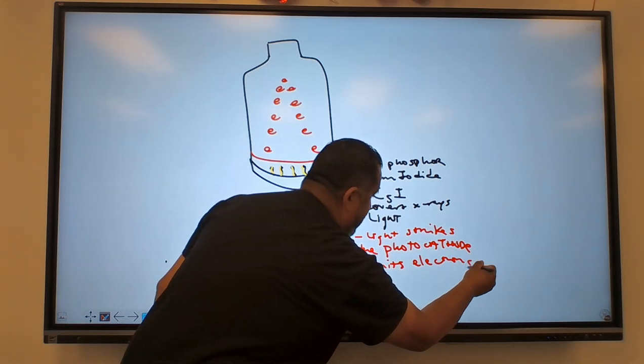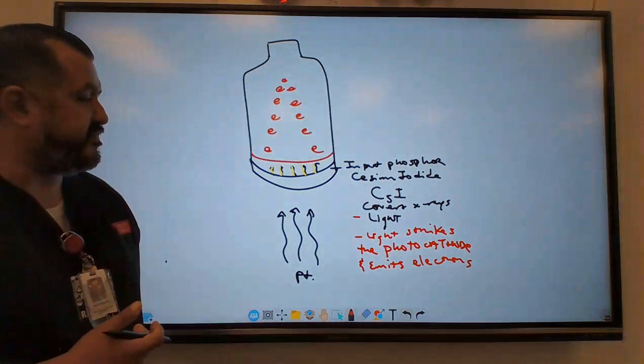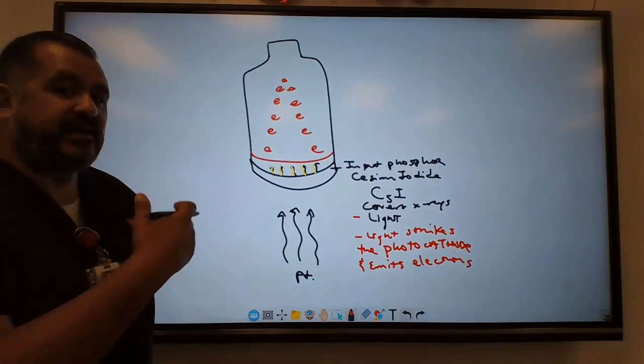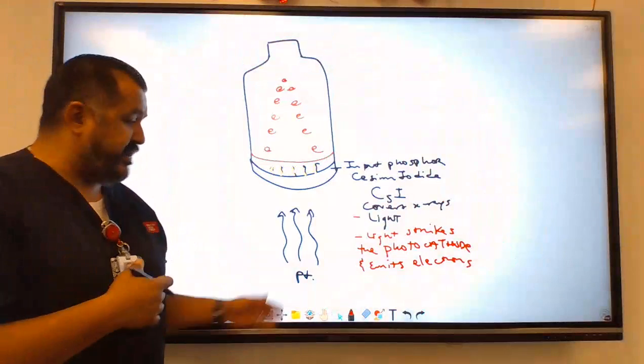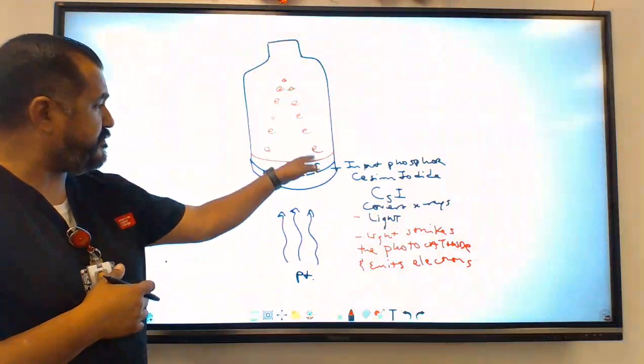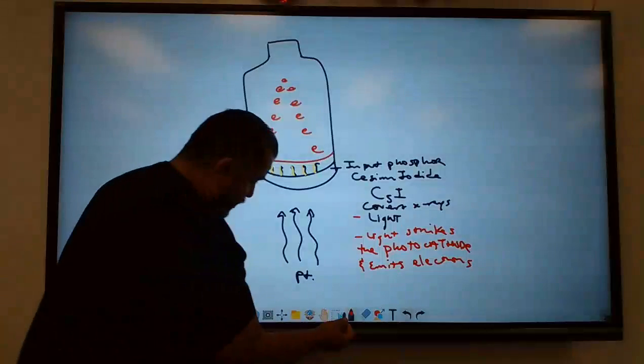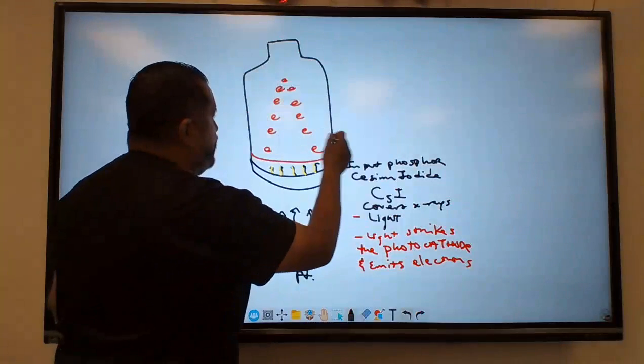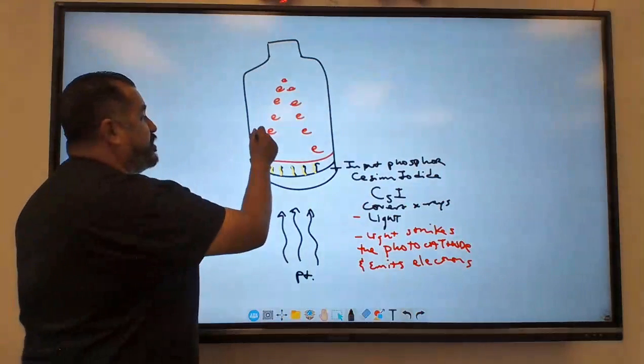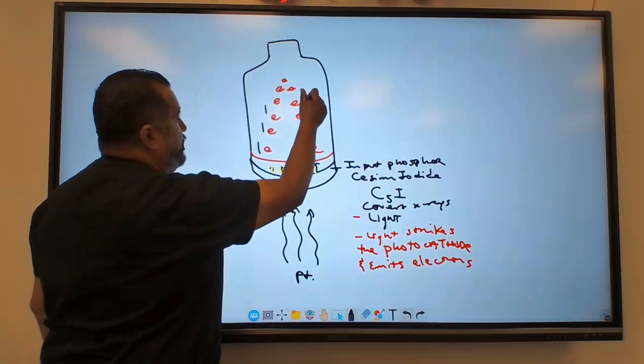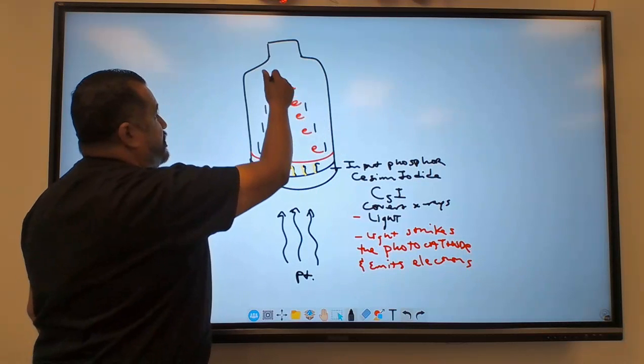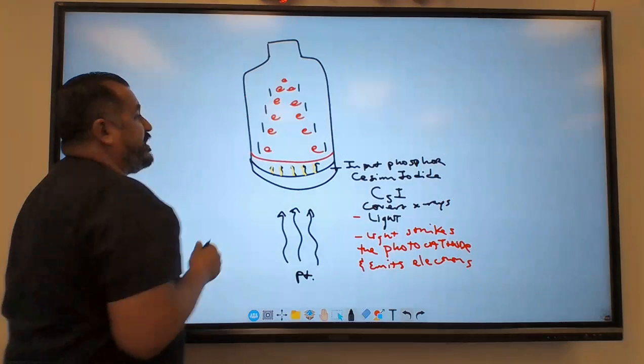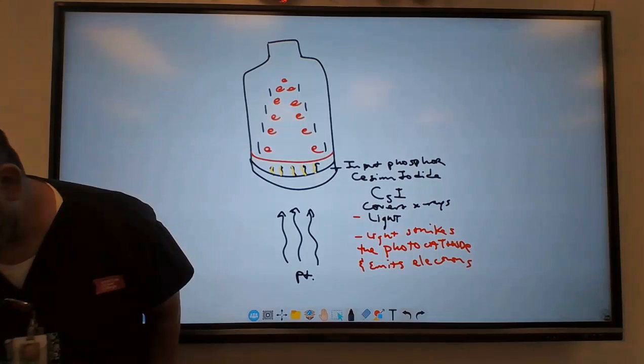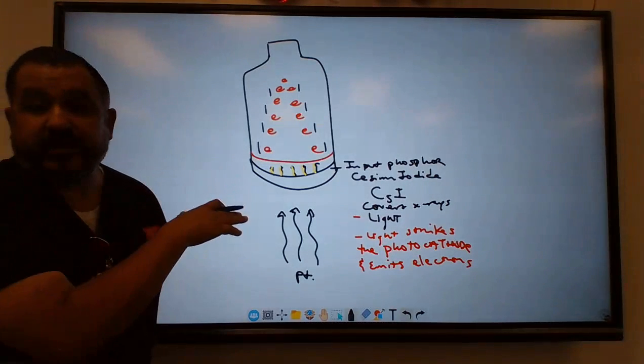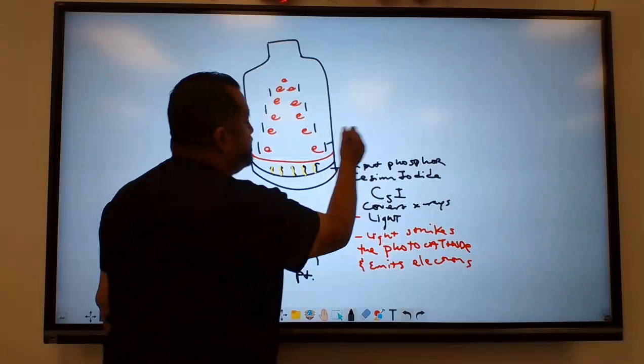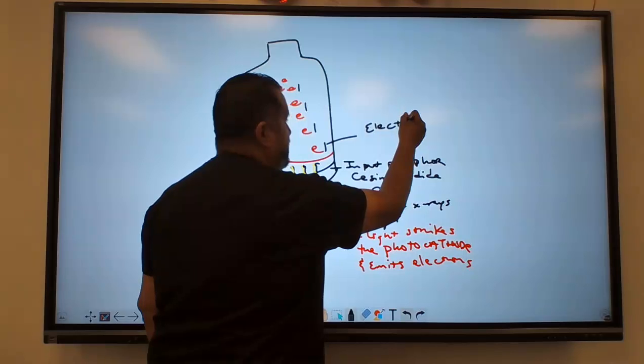Again, the photocathode is what's called a photoemissive device, and it emits electrons, almost like a cathode inside your X-ray tube. So when the electrons are traveling, they're going to be funneled—I'm going to draw a couple of these electrostatic lenses. I think the drawing only shows two, but I have a couple more here. These are called electrostatic lenses.